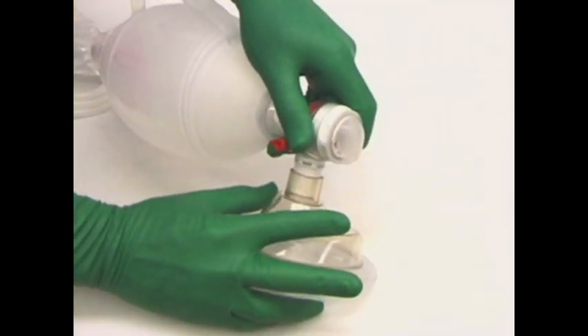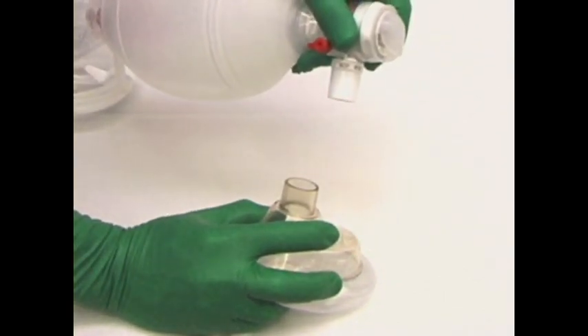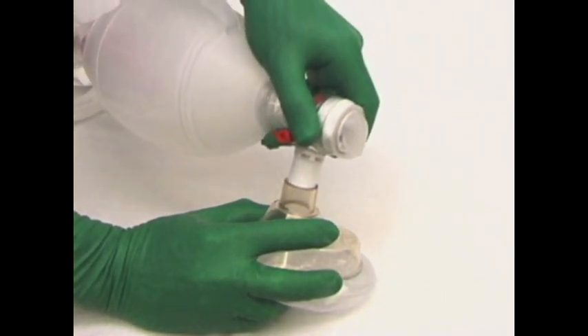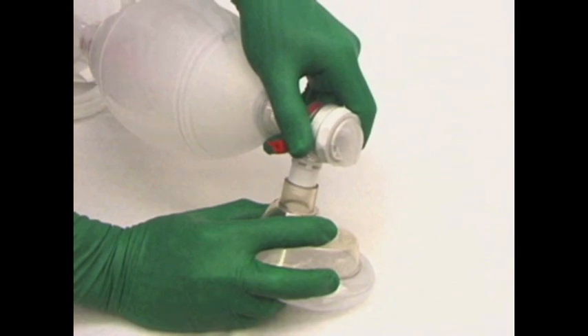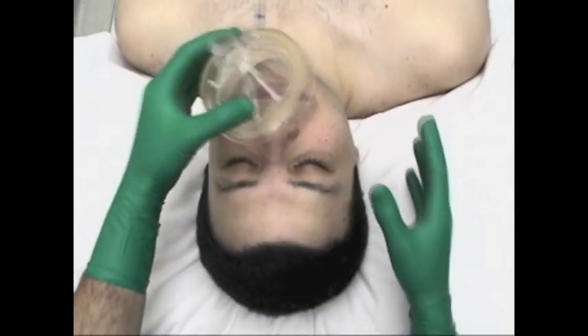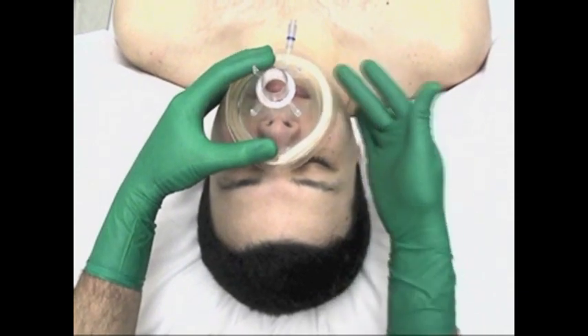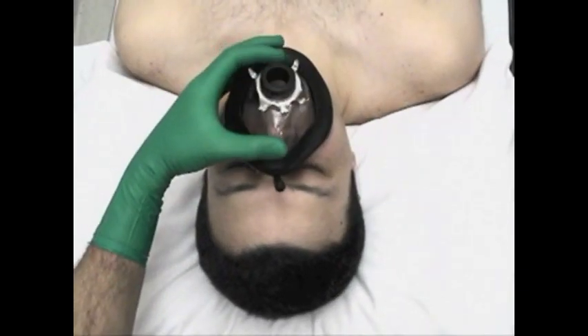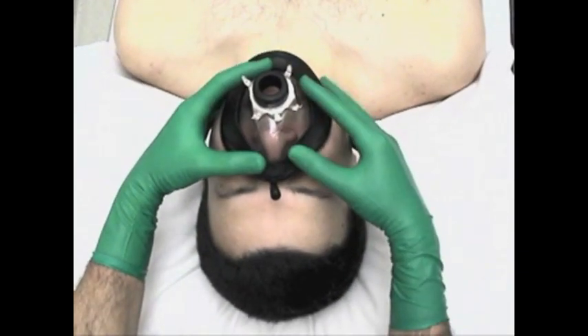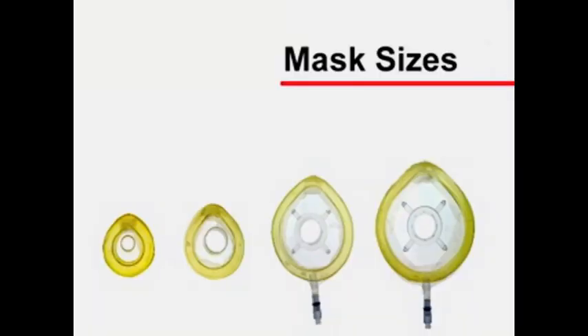The connector of the mask is a standardized 22-millimeter diameter orifice and connects the mask to a bag valve device. To maintain a good seal, it is imperative for the mask size and shape to conform to the facial anatomy. This is particularly important in the pediatric population. Thus, several masks, shapes, and sizes should be readily available.